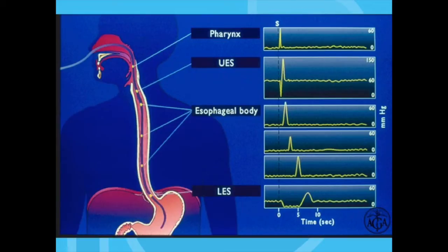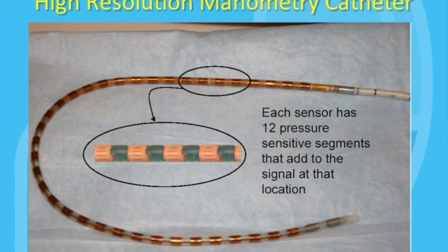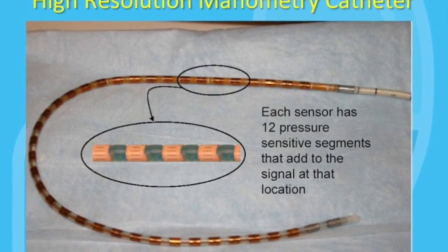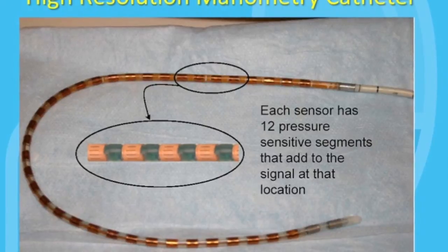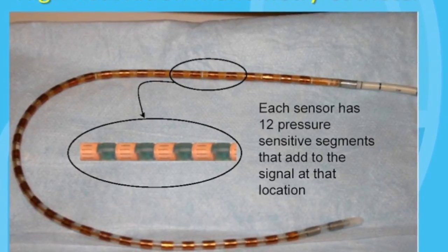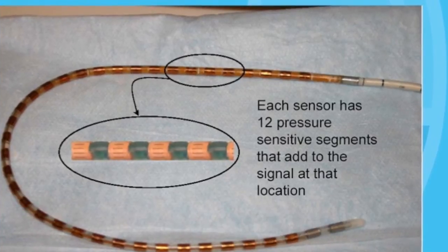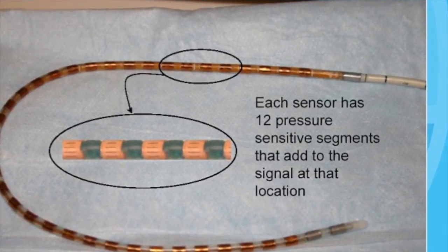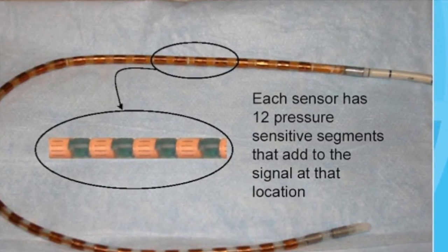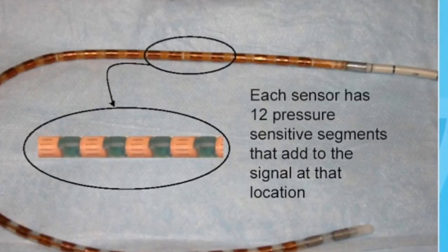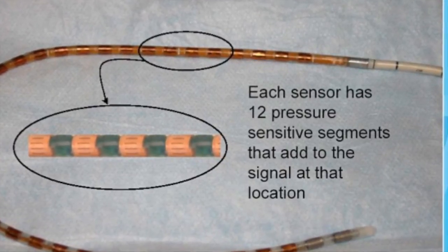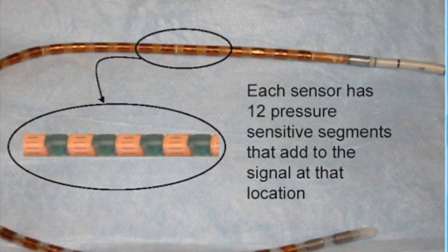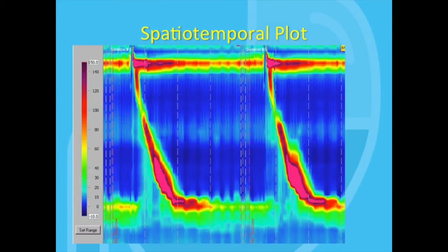You can see that there's actually a problem with this method in that there are large gaps between the pressure sensors, meaning that there's a lot of information about the pressure behavior in the esophagus that's missing. Fortunately, we now have high-resolution esophageal manometry. In this slide, you can see a modern esophageal pressure catheter that has 36 pressure sensors down its length. This generates a lot more data and a much more accurate description of the pressure behavior in the esophagus. The old pressure line graph has been replaced with a spatiotemporal plot.